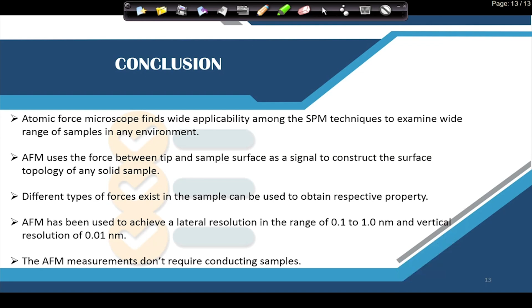So, these are the main applications of atomic force microscope, and in conclusion, what we see in this introduction is that atomic force microscope finds wide applicability among the family of scanning probe microscopic techniques to examine a wide range of samples in any environment, as here again a physical probe scans over the surface. Therefore, we do not need vacuum; we can use it in air, we can use it under liquid like the scanning tunneling microscope, and it measures the force between the tip probe and the sample surface as a signal to construct the surface topology. And as different forces exist on the sample surface, we can use the forces for measuring the respective property of the sample.